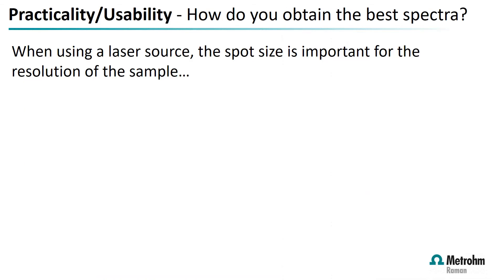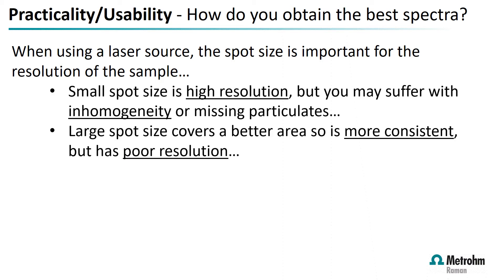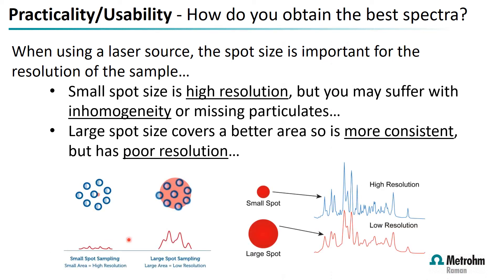Practicality and usability — how do you obtain the best spectra? When using Raman, the laser spot size is important for the resolution of the sample. A small spot size gives very high resolution, but you may suffer from inhomogeneity or miss particulates — especially in mixed powders or granular samples — where the small spot size can occasionally miss areas of interest.